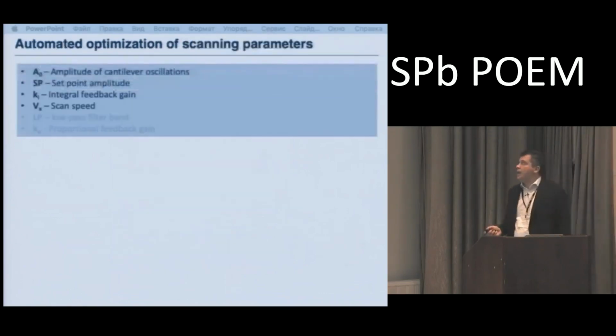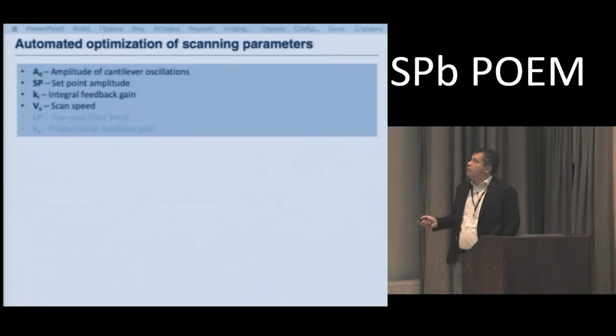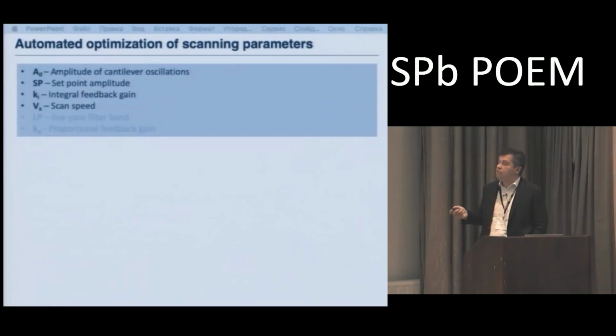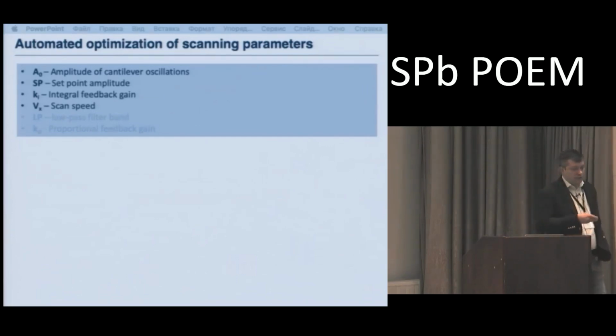So during the measurements, we actually have several parameters that influence the quality of the result and the regime of the interaction of the probe with the sample. That, in consequence, influences the results if you make some near field experiments, or experiments in more complex AFM modes. So we have the amplitude of cantilever oscillation, which can be larger or smaller, the set point value of this amplitude, the feedback gain, and the scan rate.